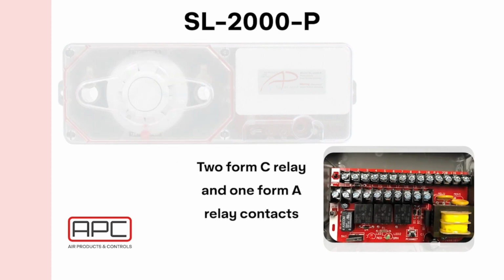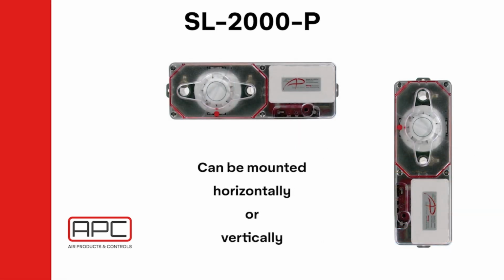The detector features 2 Form C relay contacts, allowing the detector to alarm, close dampers, and a myriad of other functions based on the application. The detector can be mounted horizontally or vertically, allowing for multiple applications, such as round ducts.